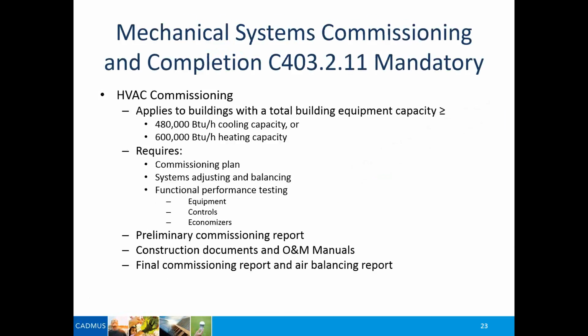Okay, so we've talked about the pieces of the mechanical system, and now the next big thing, and this is probably the biggest difference between the 2006 and 2015, is the requirement to commission mechanical systems. And this is not going to be for all mechanical systems or for all buildings. There's actually a threshold, and in your case it would apply to buildings with total building equipment capacity of 480,000 BTUs per hour cooling capacity or greater.